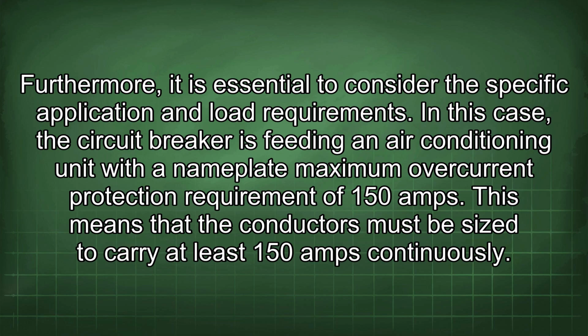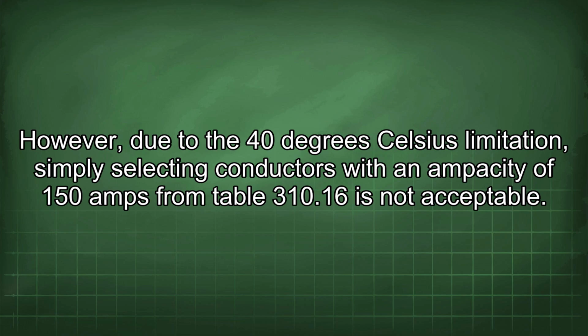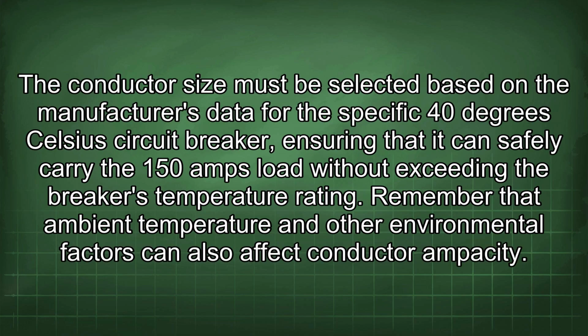Furthermore, it is essential to consider the specific application and load requirements. In this case, the circuit breaker is feeding an air conditioning unit with a nameplate maximum overcurrent protection requirement of 150 amps. This means that the conductors must be sized to carry at least 150 amps continuously. However, due to the 40 degrees Celsius limitation, simply selecting conductors with an ampacity of 150 amps from Table 310.16 is not acceptable. The conductor size must be selected based on the manufacturer's data for the specific 40 degrees Celsius circuit breaker, ensuring that it can safely carry the 150 amps load without exceeding the breaker's temperature rating.